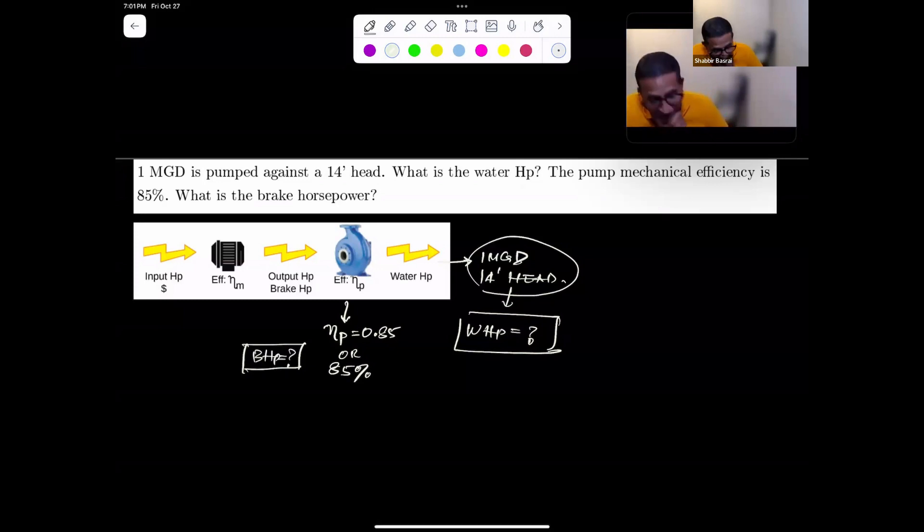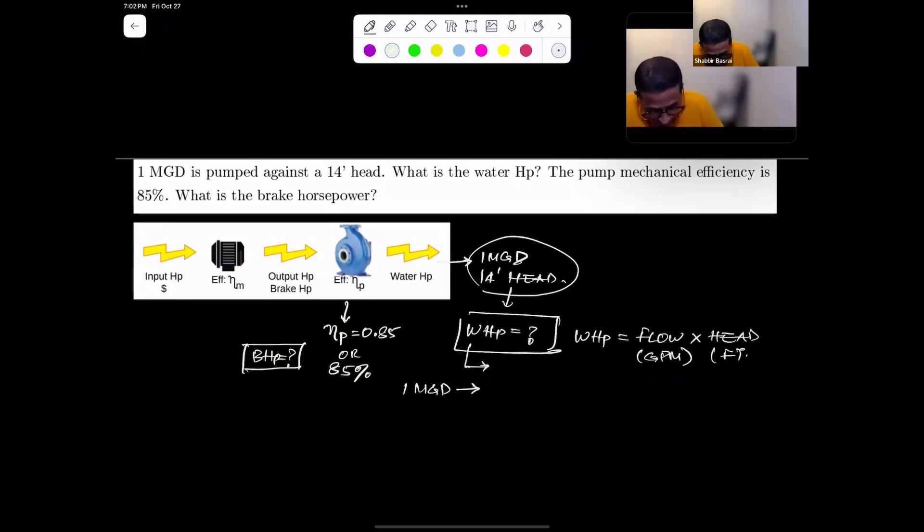In this particular case, we know the water horsepower is basically a product of your GPM times the head. Here you have a flow of one MGD, but you need the flow in GPM. Most important is that you need to write down the formula. Your water horsepower is equal to the flow in GPM times the head in feet.